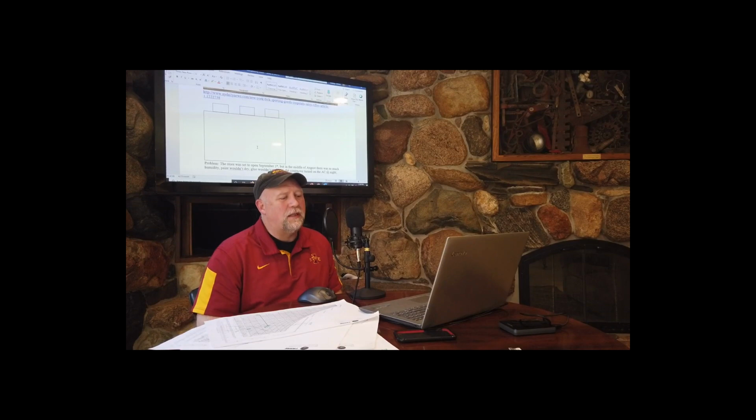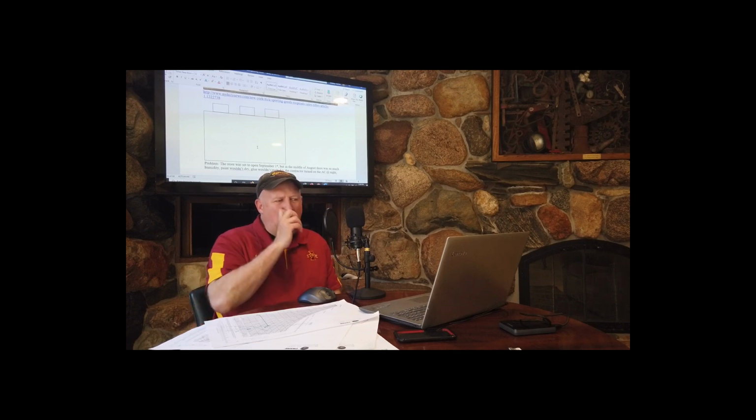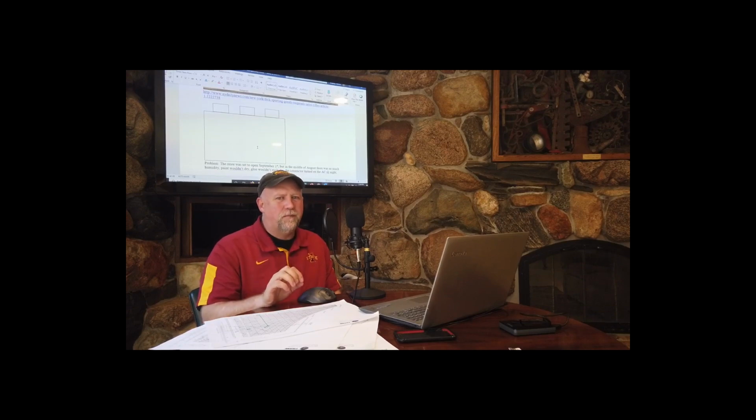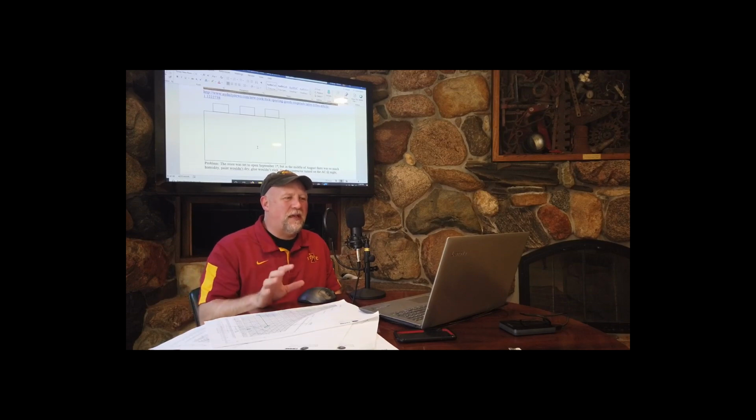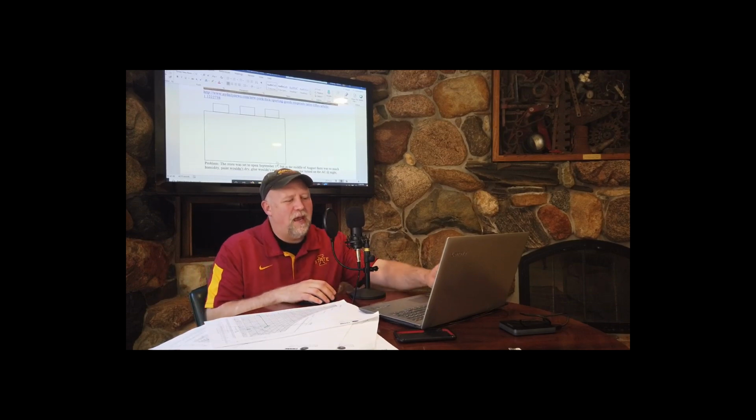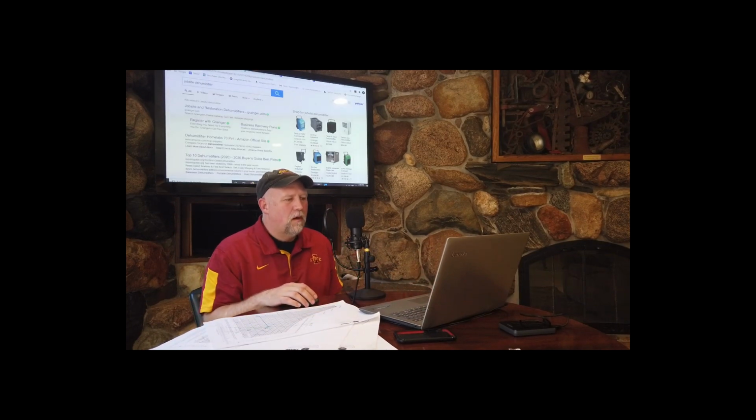Well, I gave him a few possibilities. I said, well, here are some suggestions. My first suggestion is, you don't need air conditioning, you need dehumidification. Lowering the space temperature isn't helping you any, and it's actually making it worse. You need to get yourself a job site dehumidifier. Something like this.